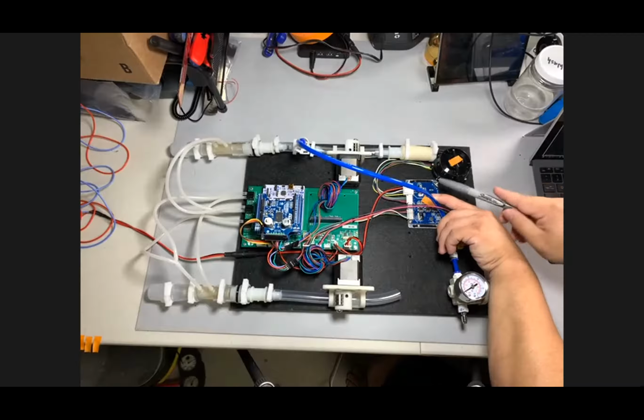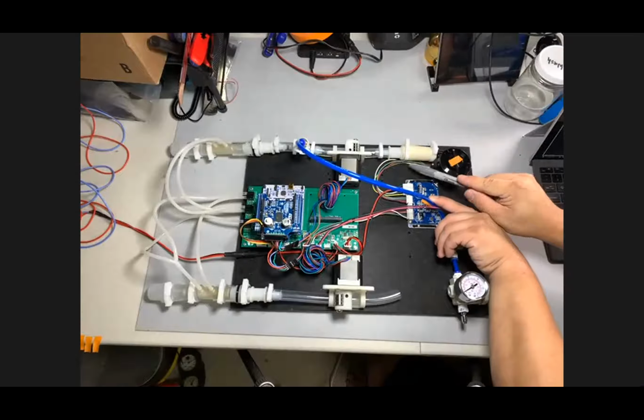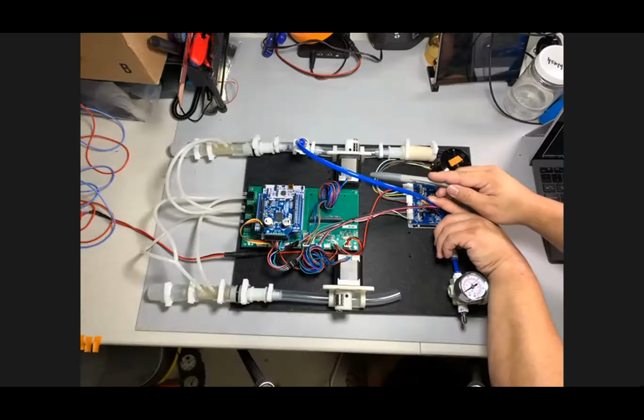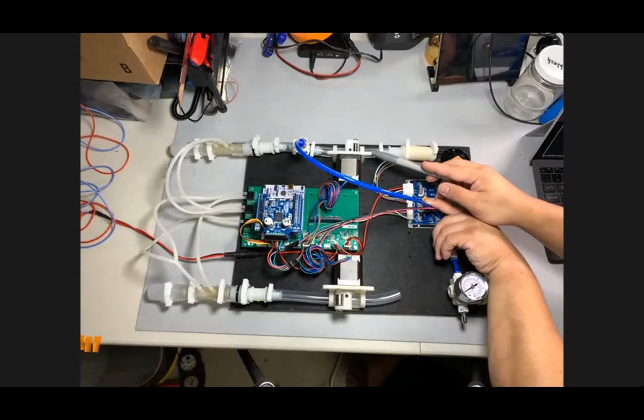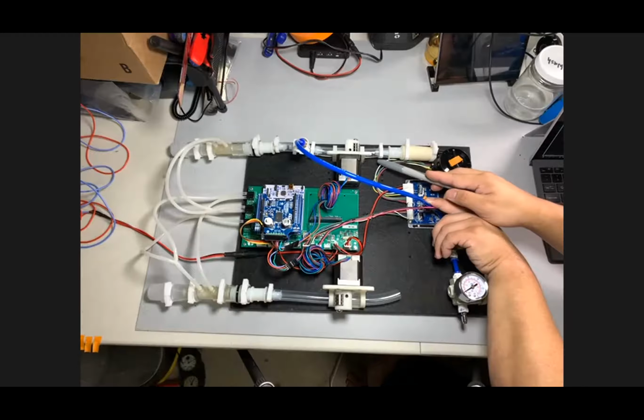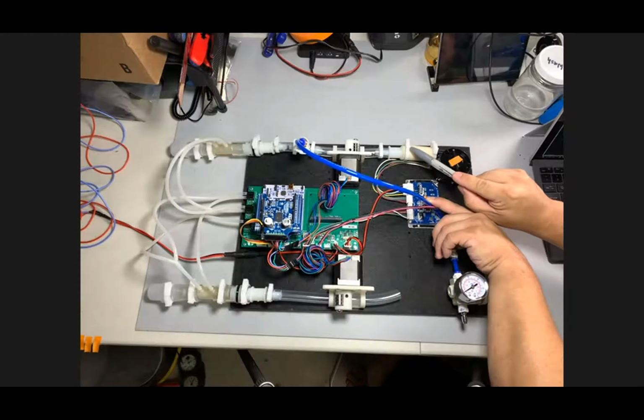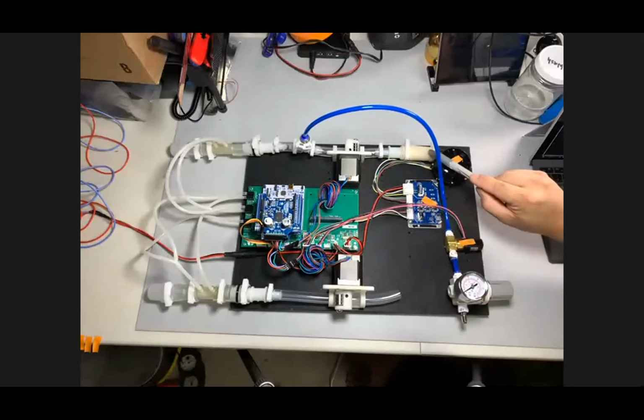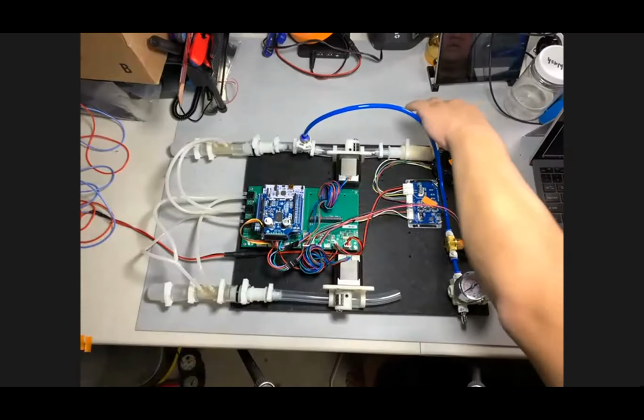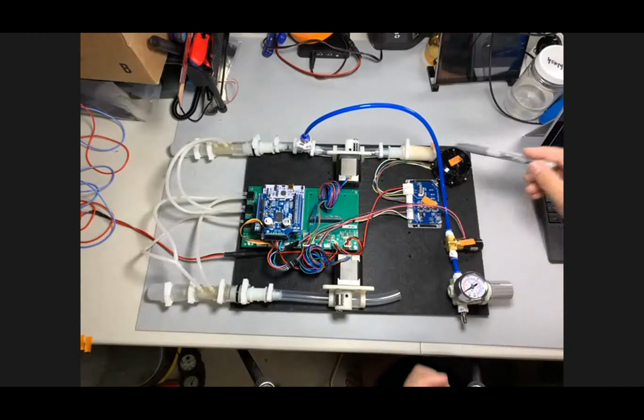So one of the things that needs a different size tubing is that this pinch valve is designed around a 5/8 outer diameter, 3/8 inner diameter soft rubber tubing, and the dynamics of this are dependent on the geometry of that tubing. So what we'll do is a step down from our 3/4 tubing here. We have an adapter, and of course all of these things will be clamped. So we have these plastic clamps here, which, if there's no objection, are what we're going to use in the final design, or in the demo design. So I'll just mark that off as one that we can see.